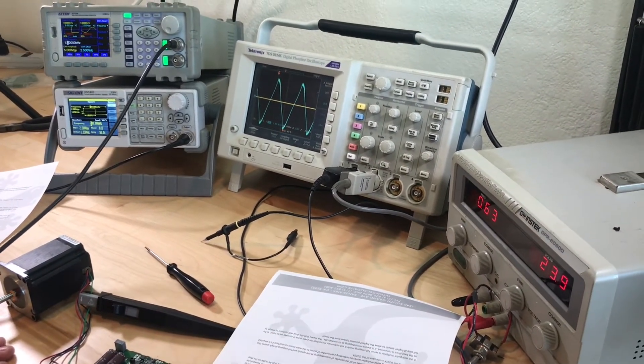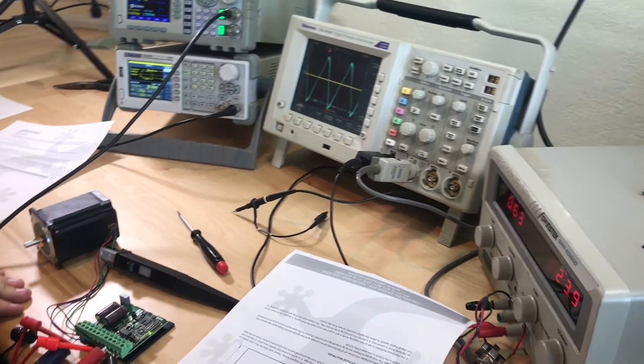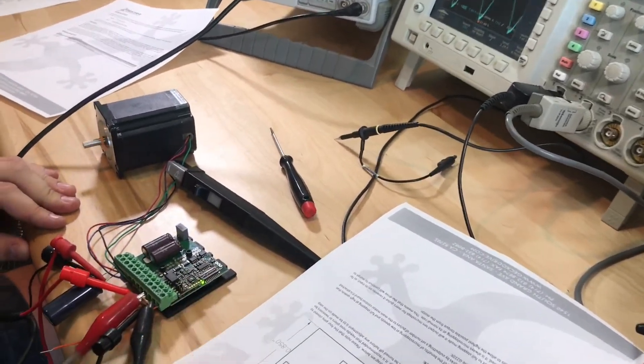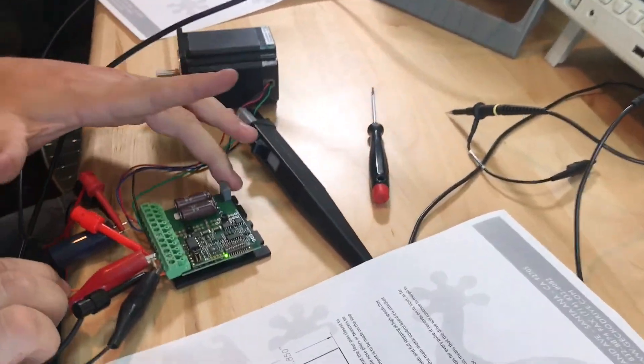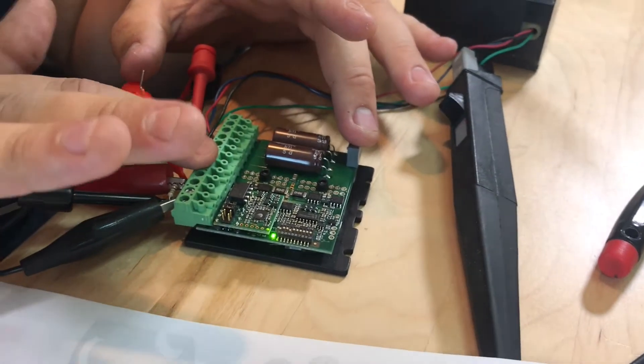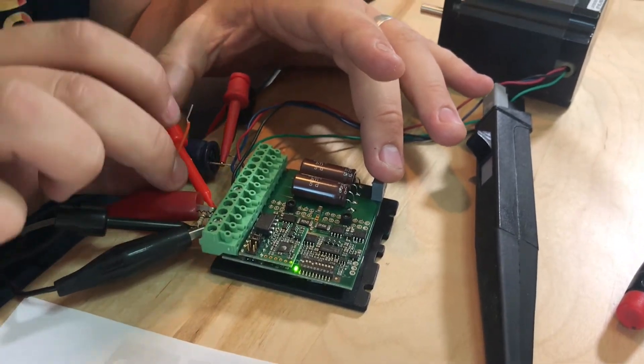One other thing that you may or may not be using is the disable terminal. If you short the disable terminal, just terminal seven to ground, which is terminal 12, it will freewheel the motor.